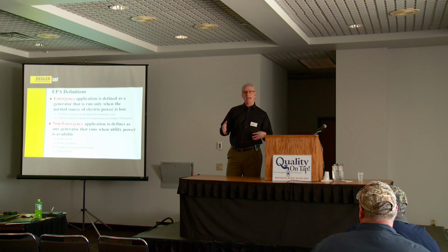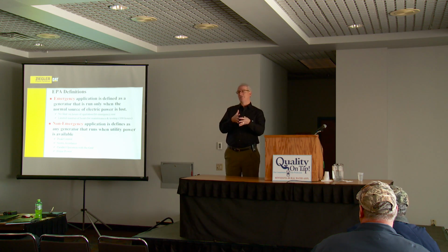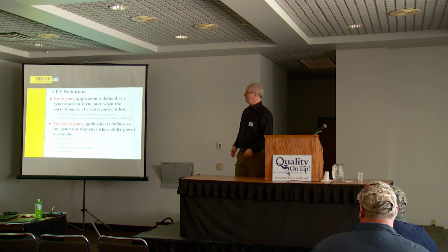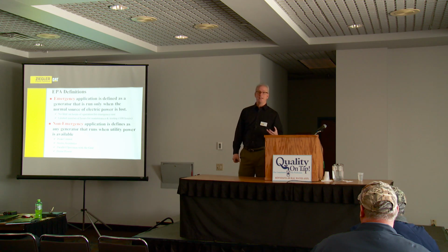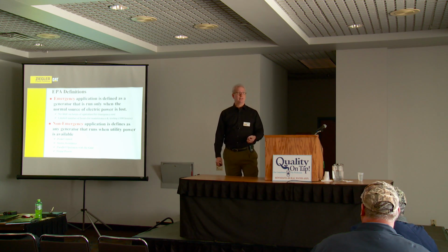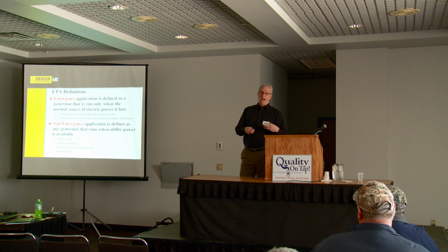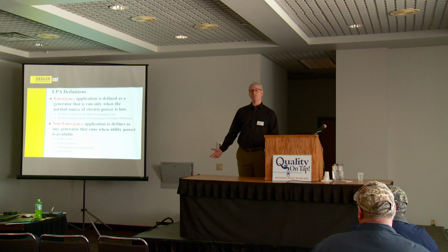But then the EPA, in making these rules, had to define things differently, or make a better definition. We'll talk about this for new engines and for existing engines as well. The EPA says that an emergency engine is an engine that only runs when the power goes out. You have an outage, the engine starts, that's fine. And you can run it however long you need to, as long as the utility power is out.